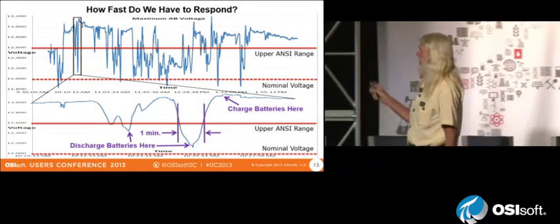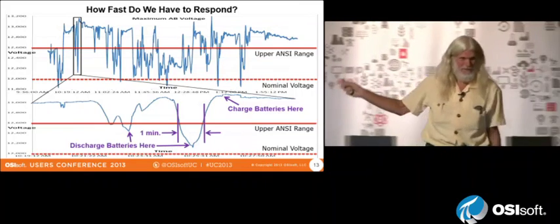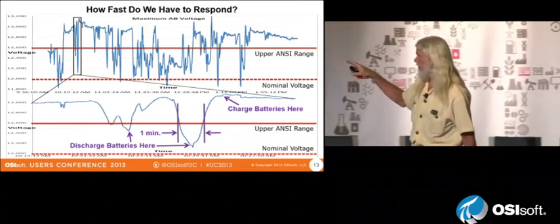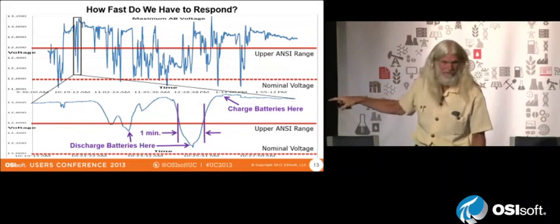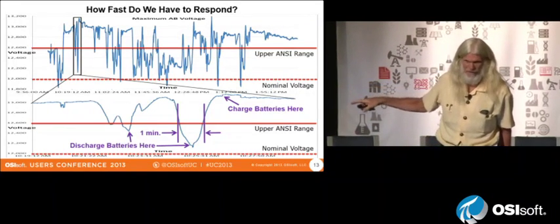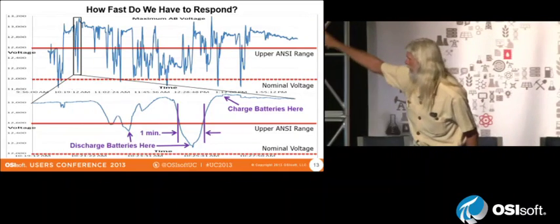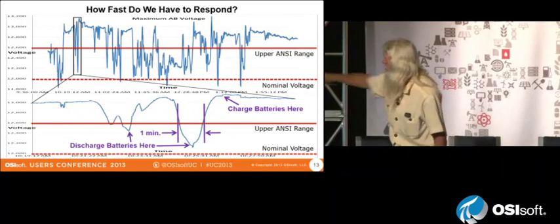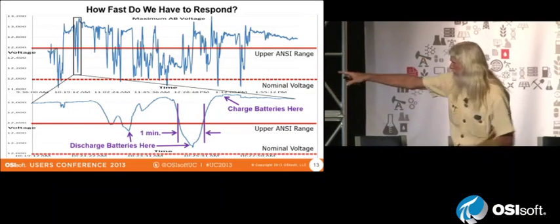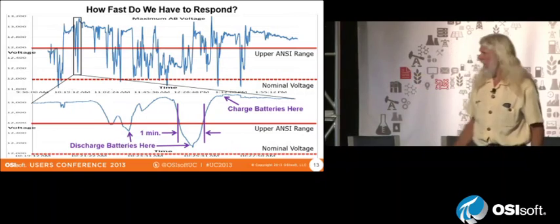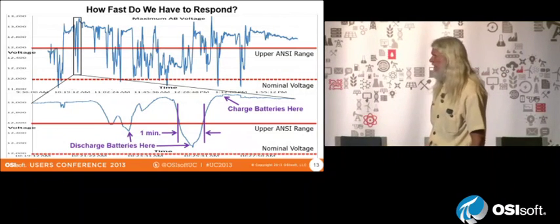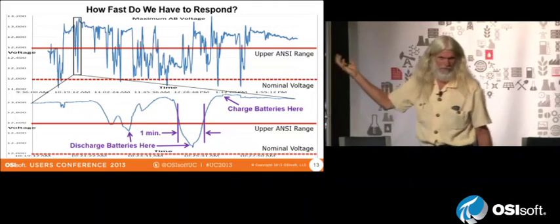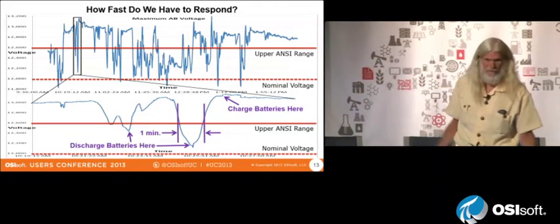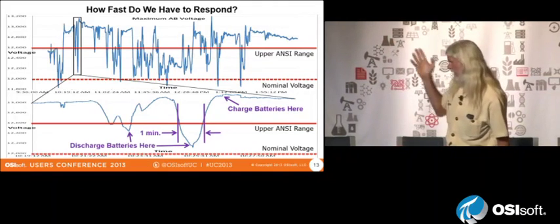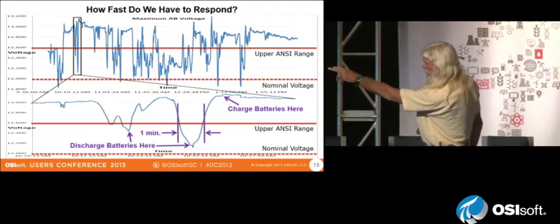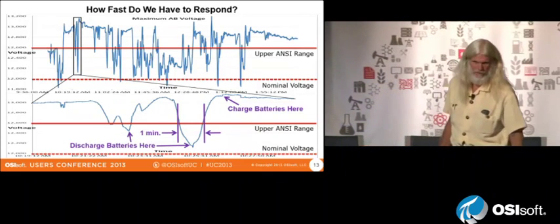Now, if you're going to stay awake for one slide in the whole presentation, this is the one you want to do it on. This is real data, what's really happening to the real power grid in Southern California with high integration of solar. This graph is expanded on the bottom part, so that whole screen is about 10 minutes, and I've blocked off 1 minute there so you can see what the solar is doing. It's actually changing the voltage of the grid, because it's not always putting out the same amount of power. The sun's coming and going, and this is real stuff happening. You can see that within a few seconds, you need to be able to respond.